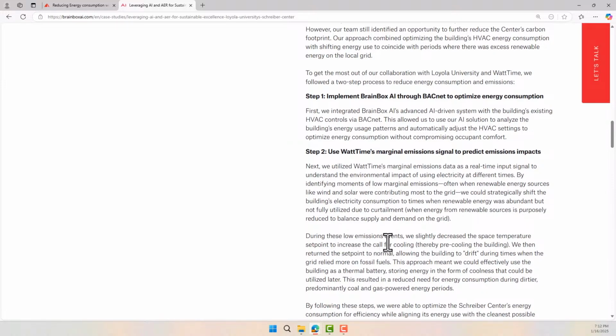During low emission events, they decreased space temperature. Low emission events means times when the electric company is consuming less electricity. So during low emissions, low electricity consumption, they decrease the space temperature set points to cool the building before it gets too hot later in the day — essentially pre-cooling the building.